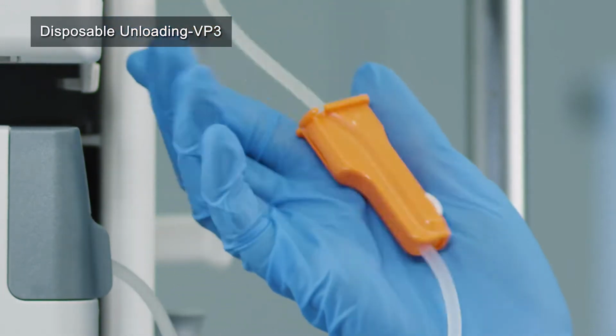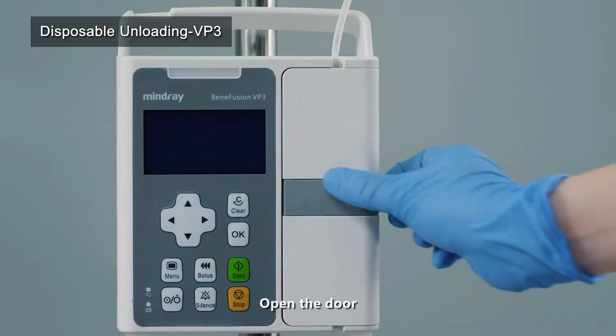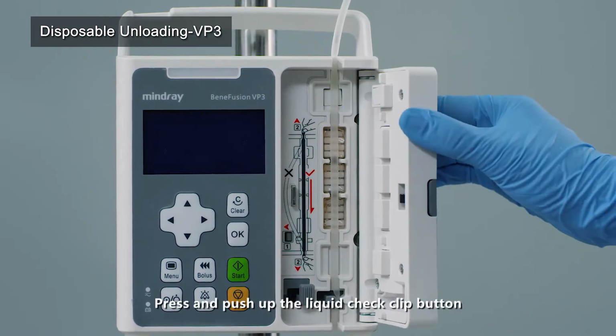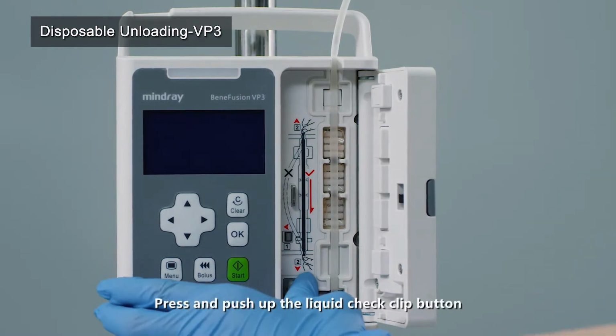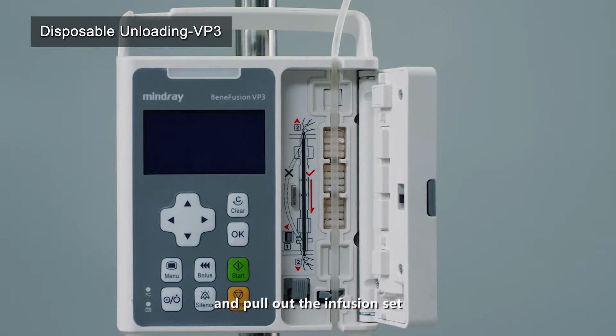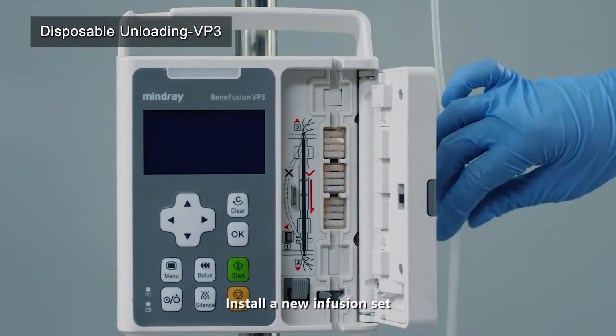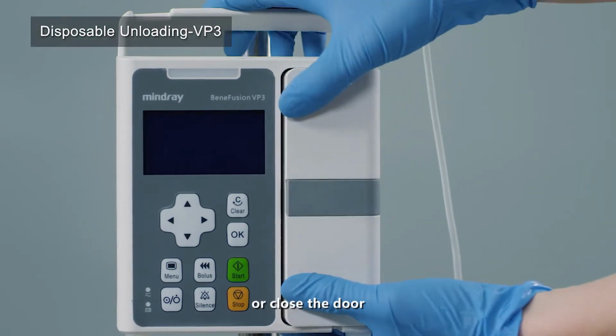For infusion pump, close the roller clamp or Robert clamp. Open the door, press and push up the liquid check clip button, and pull out the infusion set. Install a new infusion set, or close the door.